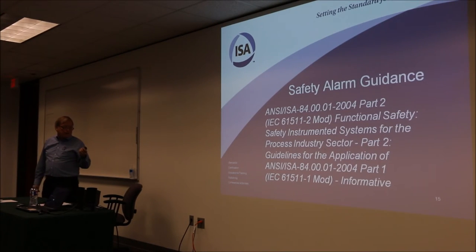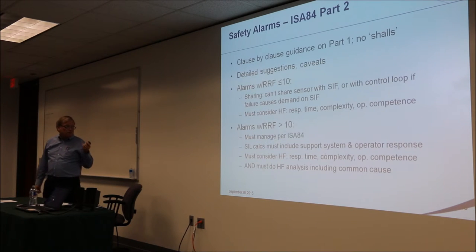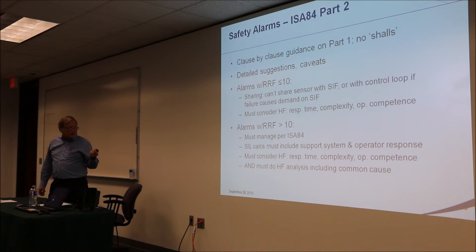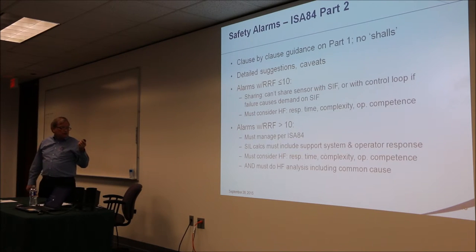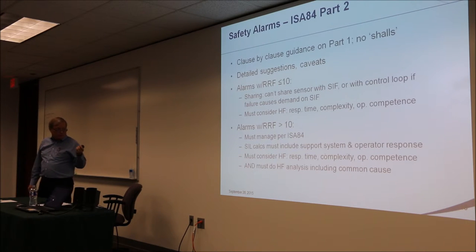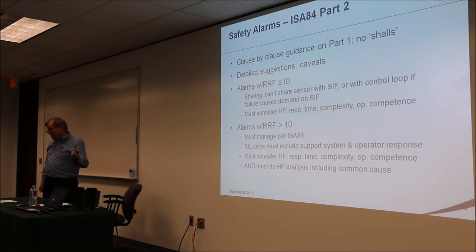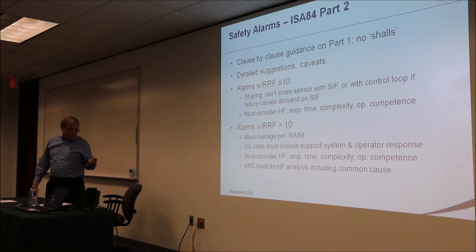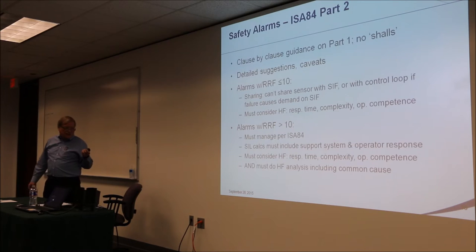Part 2 is non-normative — it doesn't have shall statements — but it has important clause-by-clause guidance on Part 1, with several clauses that touch on safety alarms. Most notably, it provides advice on risk reduction claims for less than 10 and greater than 10. ISA 84 clearly states that any function claiming more than a risk reduction of 10 needs to be managed per ISA 84. Part 2 echoes that requirement and points out that SIL calculations need to include the operator and the support system — power, logic solver, display screens — and that a human factors analysis including common cause is required for risk reduction greater than 10.